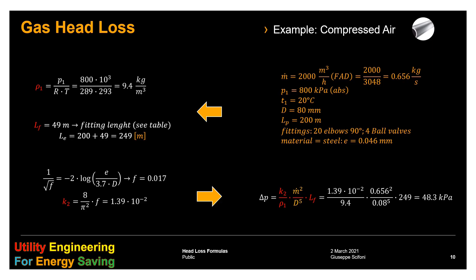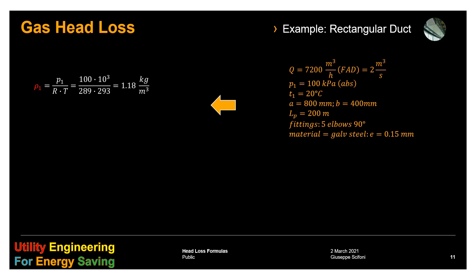The second example is for a ventilation duct. Here the pressure is atmospheric or nearly, at room temperature. The pipe is not round but rectangular. The length and the fittings are also given. We get first the density of the air, which is 1.18 kg per cubic meter. Then we need to calculate the area, the cross-sectional one, in square meters, and the equivalent diameter, using the formula for the rectangular ducts. And this is expressed in millimeter, 533. By means of the material roughness E, 0.15 millimeter, and the diameter, we can calculate the equivalent length and also the friction coefficient F, 0.015.